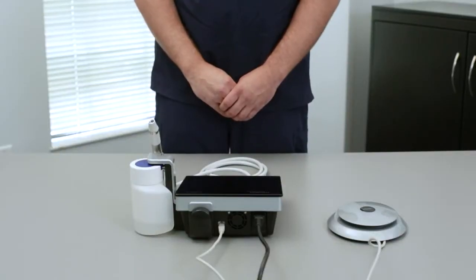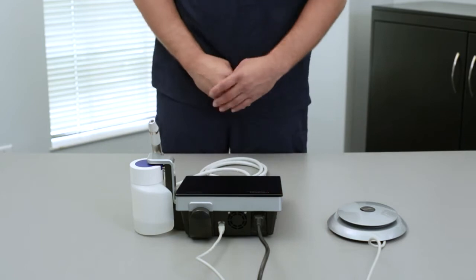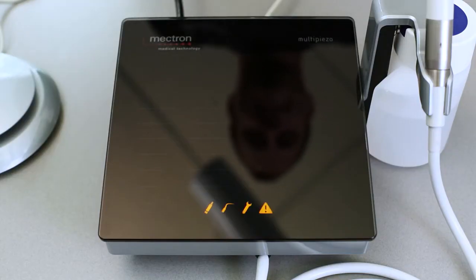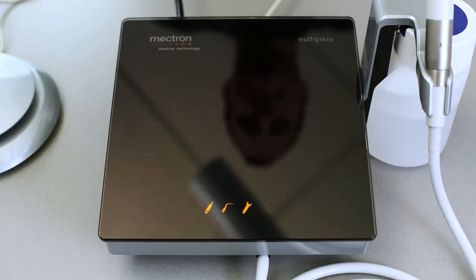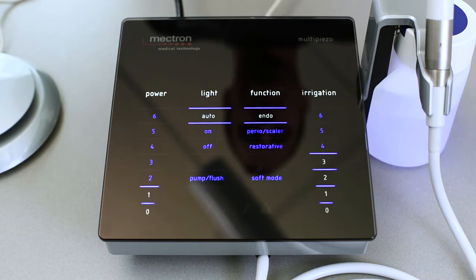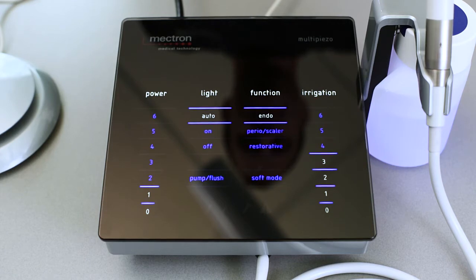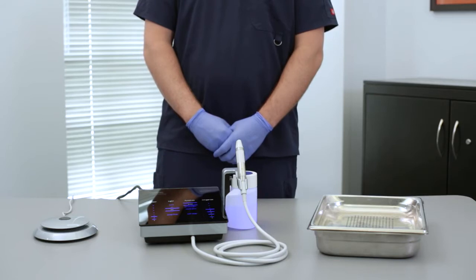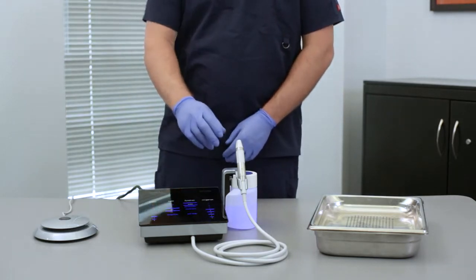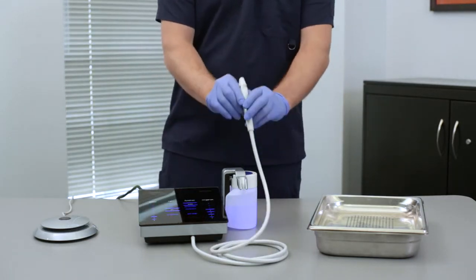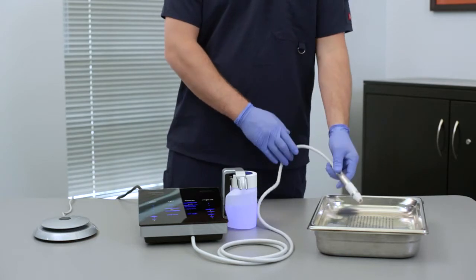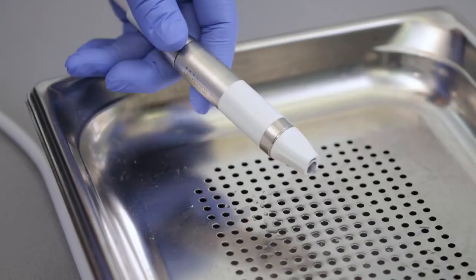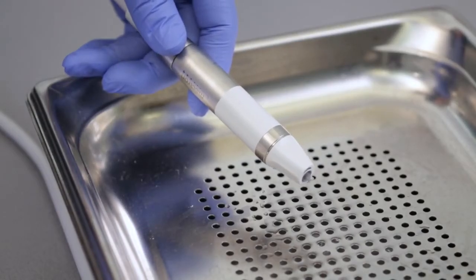Press the power lever on the left side of the device to the on position. The device will beep and flash through the warning signals at the bottom of the display. The device default settings are Power Level 1, Light Auto, Function Endo, and Irrigation 3. The first step to prepare for a procedure is to prime the handpiece with irrigation. Make sure to aim the tip of the handpiece toward an area where it's okay to deploy water, such as a sink, bowl, or cup.